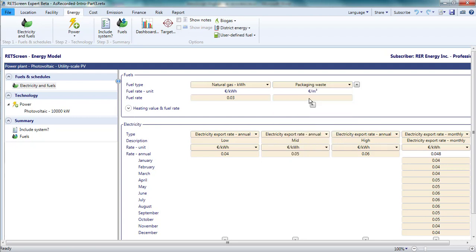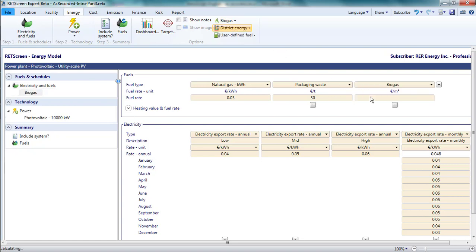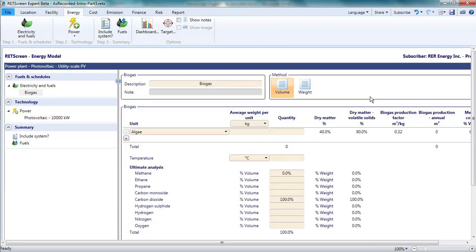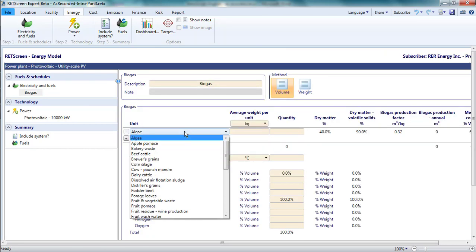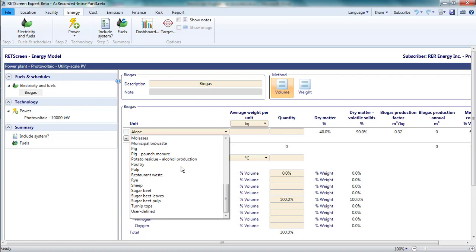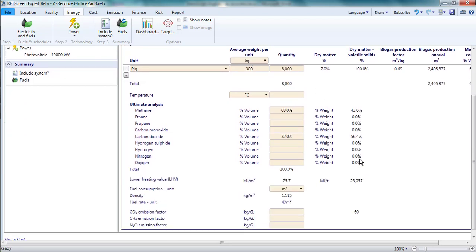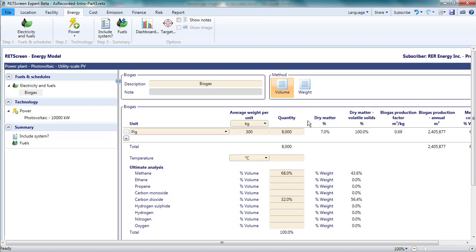If I don't find the fuel I am looking for in my drop-down list, I have further options available from the menu bar. For example, if I had a reciprocating engine that ran on biogas, I could pick that. This would add biogas to my list of fuels, and also add a new window for specifying the sources of the biogas. Here I will assume that it is a pig farm. From this, RETScreen would estimate the ultimate analysis of its components, the heating value, and the emissions factor. I could overwrite the values suggested by RETScreen.